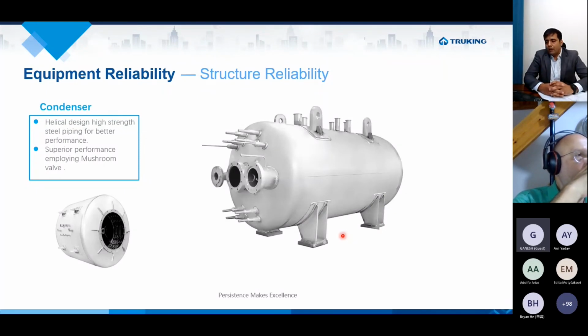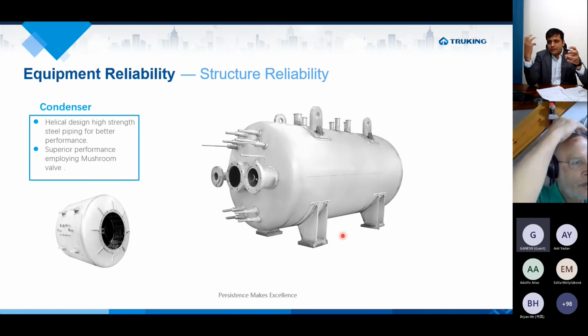The job of the condenser is to provide the surface area for ice trapping. When we evaporate the solvent from the product, it has to be trapped somewhere. So the compressor compresses the refrigerant, and when the refrigerant enters the condenser, it encounters the larger surface area, and the gases expand quickly and cause a minus 75 degrees temperature in the condenser. And once the isolation wall between chamber and condenser is open, the solvent vapors are directly trapped inside the condenser, the cycle is processed further, and you have a lyophilized product in the chamber.